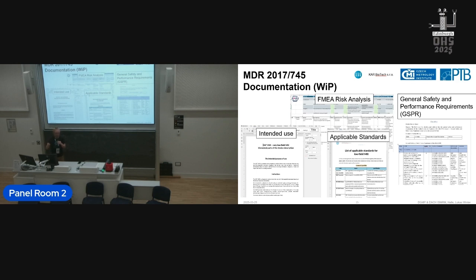But what we can do, and what we're doing within our projects, and here we work together with a notified body, which is the Czech National Metrology Institute that recently got accredited as a notified body, is to provide technical documentation for the system, that will also be released and shared. So again, it's about lowering this hurdle to make it as easy as possible to transition this technical innovation device into the clinic.